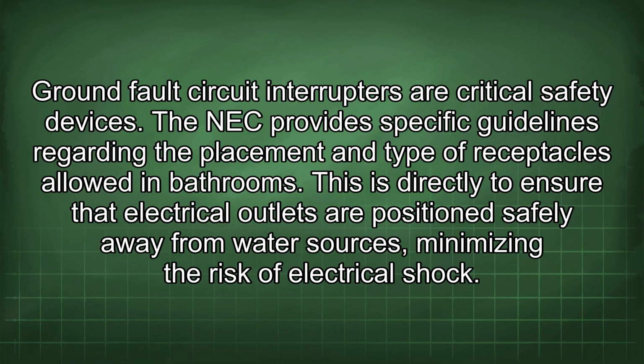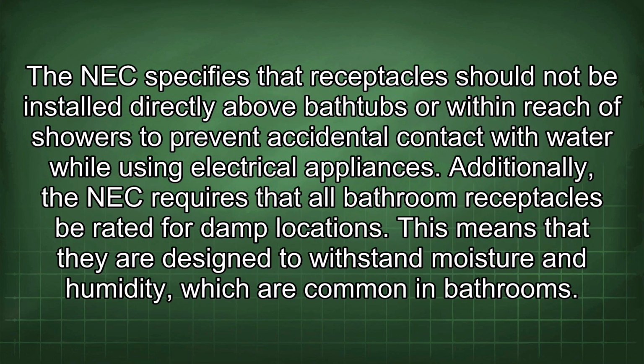The NEC provides specific guidelines regarding the placement and type of receptacles allowed in bathrooms. This is directly to ensure that electrical outlets are positioned safely away from water sources, minimizing the risk of electrical shock. The NEC specifies that receptacles should not be installed directly above bathtubs or within reach of showers to prevent accidental contact with water while using electrical appliances.